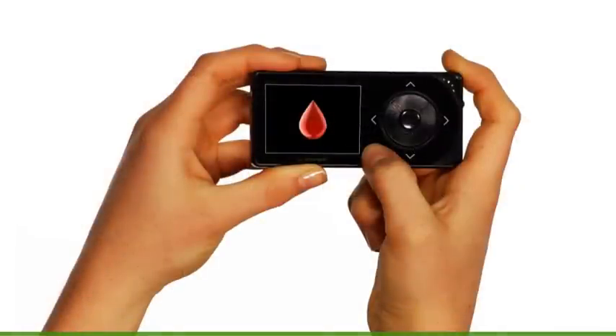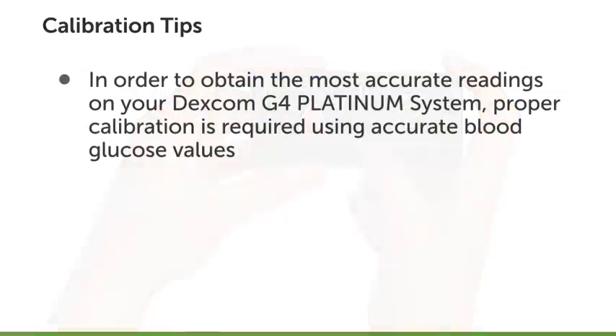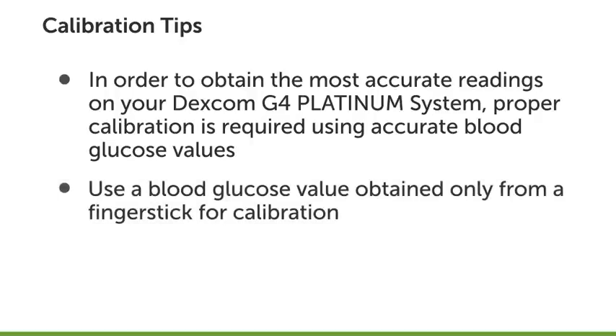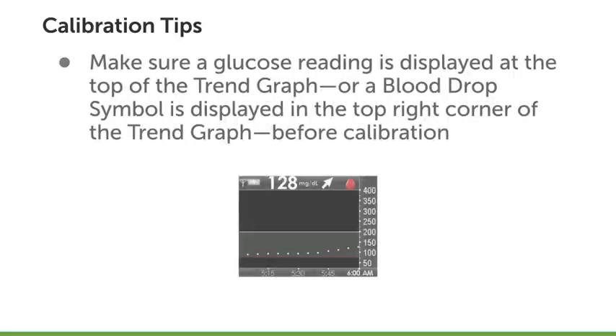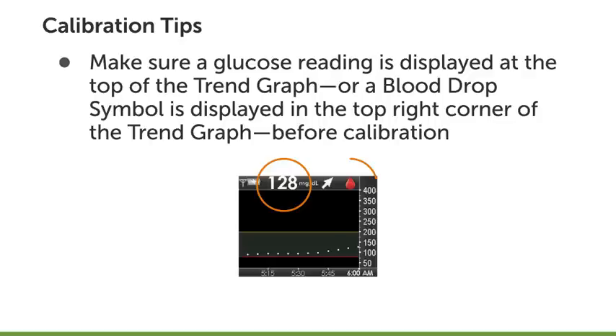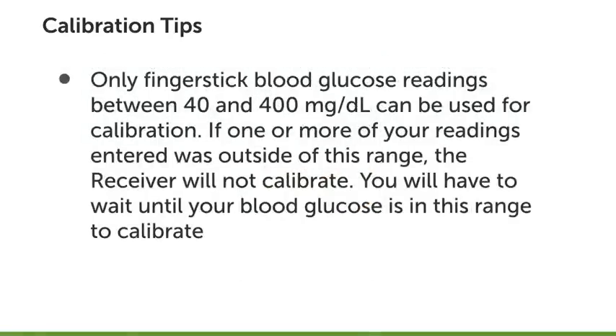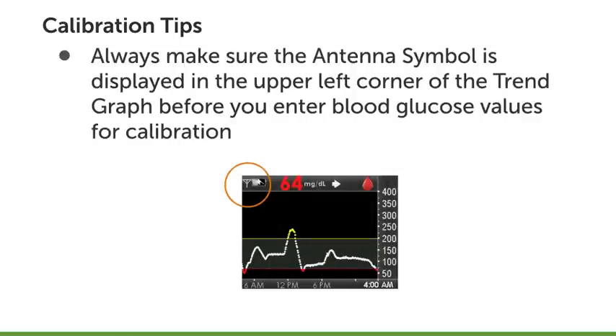Before we move on, let's go over some calibration tips that are important for you to remember. In order to obtain the most accurate readings on your Dexcom G4 Platinum system, proper calibration is required using accurate blood glucose values. Use a blood glucose value obtained only from a fingerstick for all entered calibrations. Make sure a glucose reading is displayed at the top of the trend graph, or a blood drop symbol is displayed in the top right corner of the trend graph before entering a calibration. Only fingerstick readings between 40 and 400 milligrams per deciliter can be used for calibration. If one or more of your readings entered was outside of this range, the receiver will not calibrate. You will have to wait until your blood glucose is in this glucose range to calibrate. Always make sure that the antenna symbol is displayed in the upper left corner of the trend graph before you enter blood glucose values for calibration.